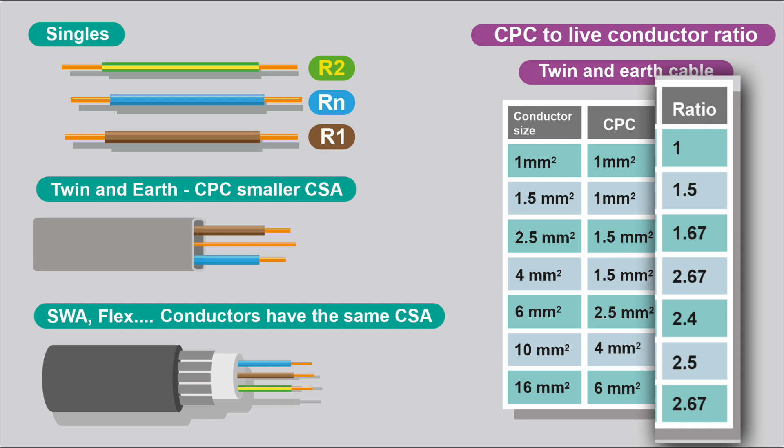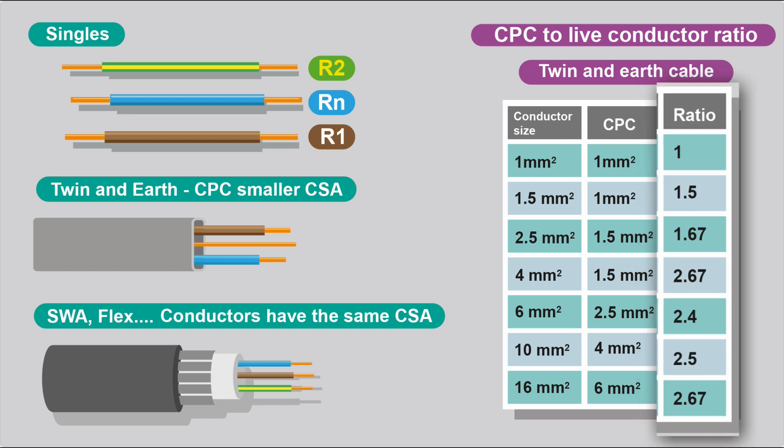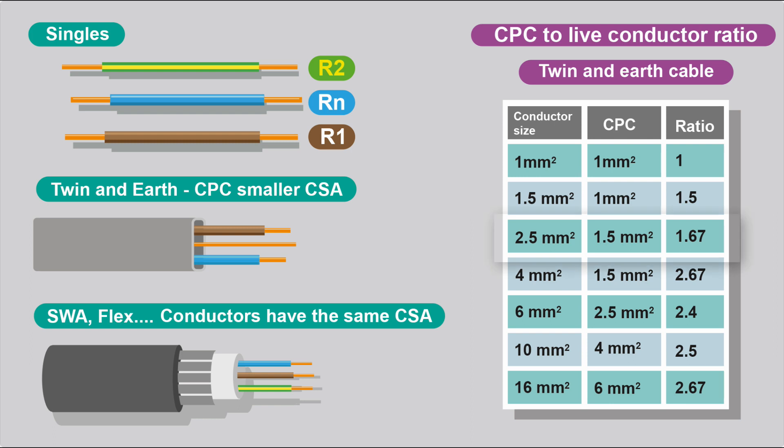We'll take the example of 2.5mm² cable. So if you've got 2.5mm² twin-and-earth, the live conductors will be 2.5, the CPC will be 1.5. So the ratio, the difference between the CPC and the line conductors is 1.67. And we can verify the resistance readings we are getting correlated to the length of cable.